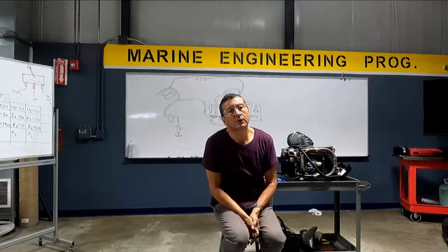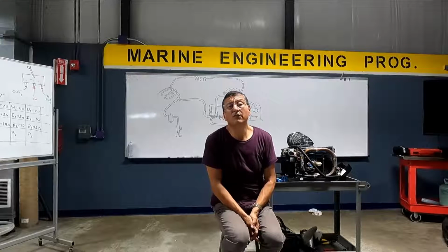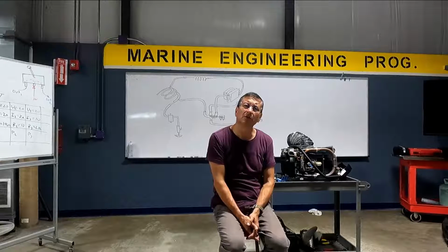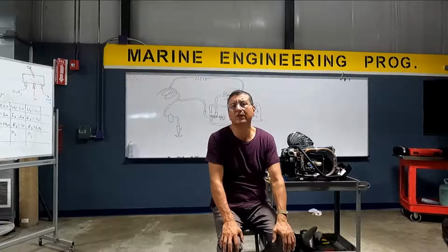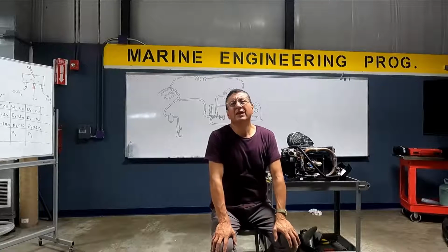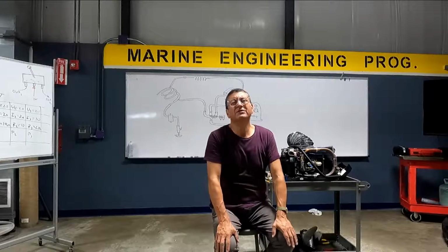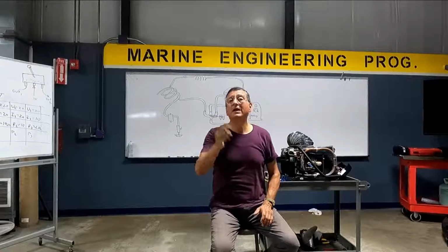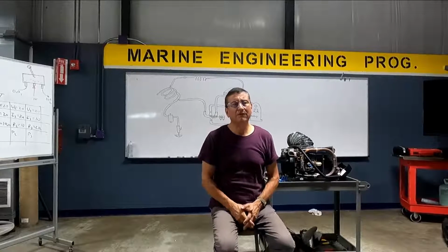If you have high pressure in the low pressure side, what is it? No, it's not possible. That's the regulation of the expansion valve. But what would be an issue? The expansion valve's bad? Yeah, probably. Normally, problems are related with the expansion valve.